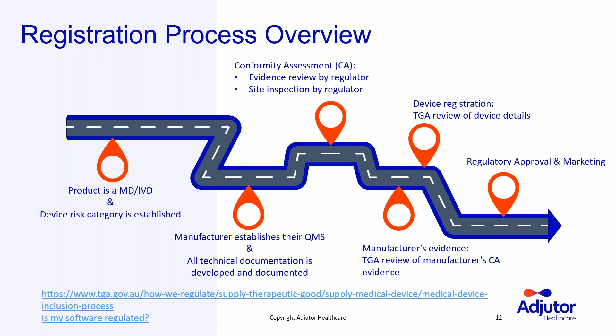In terms of timelines, the time frame for a device registration in Australia, as you will see on this slide, can vary greatly. It depends on the type of overseas evidence and the device risk category, among others. Regarding the conformity assessment application, the TGA target timeframe is actually 1 year, but they used to use 255 working days. This step is not applicable if the product has a CE mark or is the lowest risk class 1 device. The next step is the manufacturer's evidence. This is a minor administrative process, usually completed within a couple of weeks. And similar to the previous one, it is not required for class 1 devices. And last is the device registration step. After this process, you will be able to start marketing or launching the product.